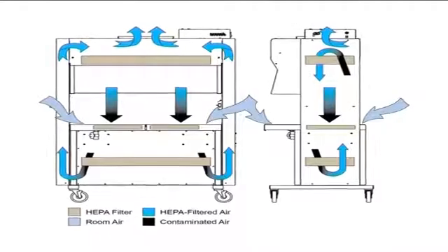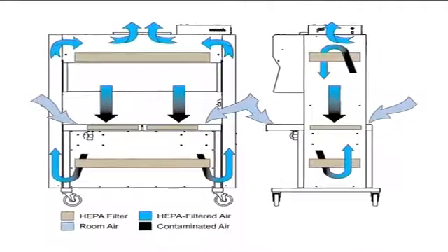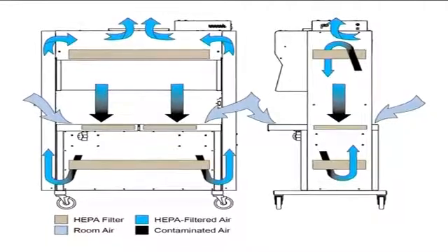The air stream at descent velocity moves essentially in a parallel pattern, so that the cleanliness of the air is independent of activities occurring down or cross stream. Undoubtedly, laminar airflow is the most important part of laminar flow clean benches to provide an environment free from microorganisms moving toward the workspace, with excellent and consistent results.